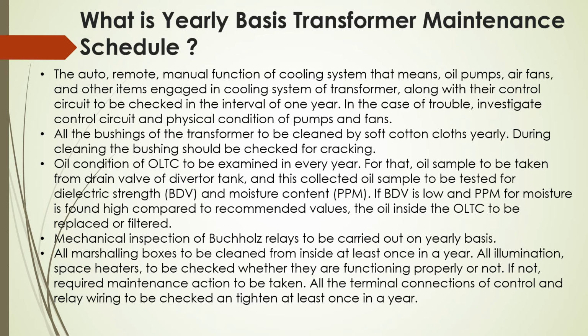All the bushing of transformer to be cleaned by soft cotton cloths yearly. During cleaning, the bushing should be checked for cracking. Oil condition of OLTC to be examined every year. For that, oil sample is to be taken from the drain valve of the diverter tank and this collected oil sample to be tested for BDV strength or dielectric strength and moisture content. If the BDV is low and ppm for the moisture is found high compared to the recommended value, the oil inside the OLTC to be replaced or filtered.